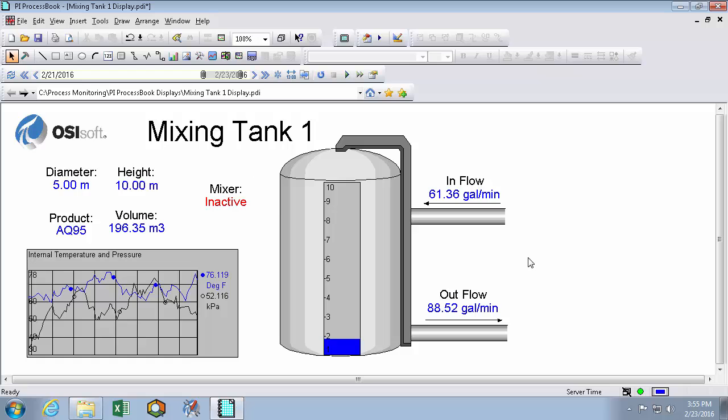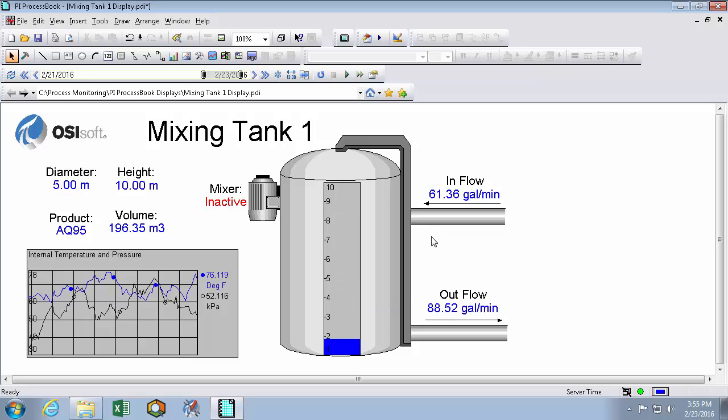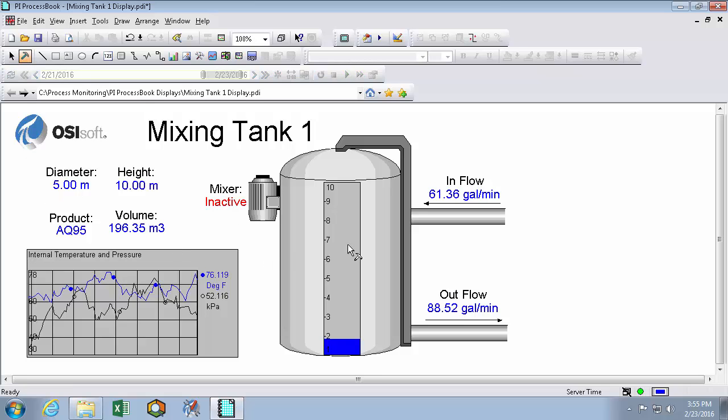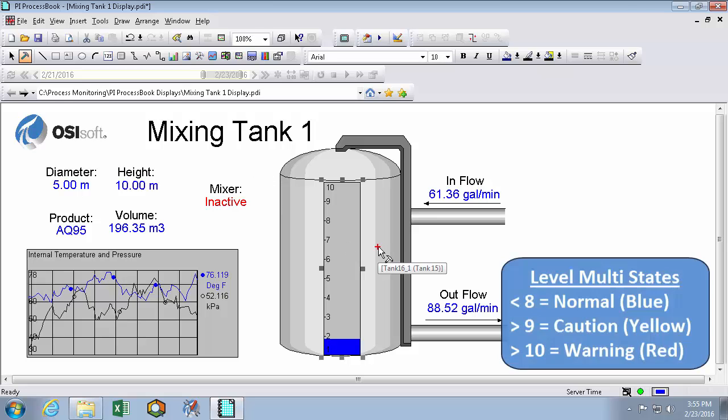Something else that's really important to my process is this level here. This level, like the one in my boiler overview display, is at risk of overflowing when it gets too high. So we'll convert it into a multi-state symbol. But this time I'm going to use three states. The first state will be a normal operation state, and that will go from 0 to 8. And I'll keep it this blue color.